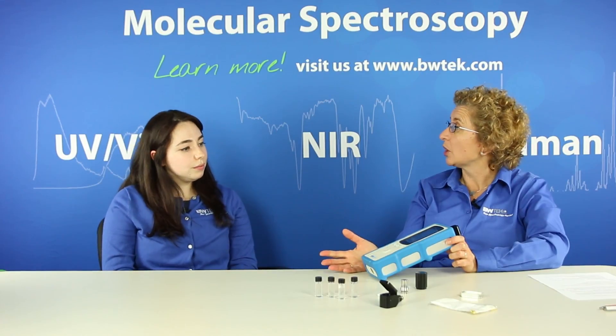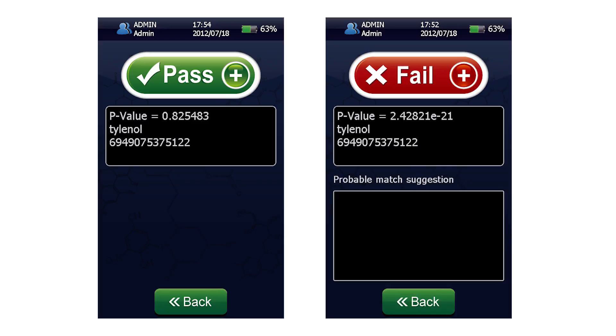What about the benefits of identification mode? Identification is quite robust — it's a multivariate method, so it's more sensitive to small changes in a fingerprint. So if you have a contamination of a sample, or samples that may be very similar chemically and therefore have similar Raman fingerprints, you can get a passing or failing result if it's not what it's purported to be.